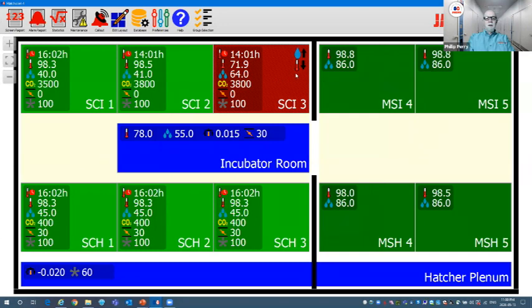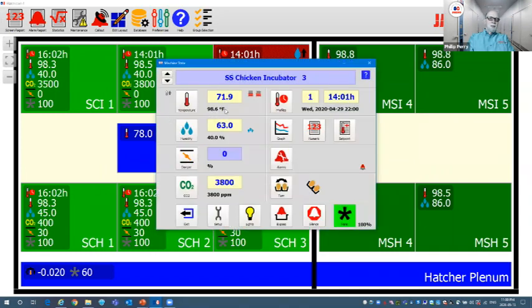This machine is still in alarm. It has a low temp at this time and a high humidity. So when I changed this, we went from a 72 degree machine in standby mode, and now it's warming up. Both heater bars are on, showing that we had a high temp alarm recovered. This is showing a low temp alarm on both the front of the machine and the rear, and we also have low humidity at this time. We have an active alarm showing here.